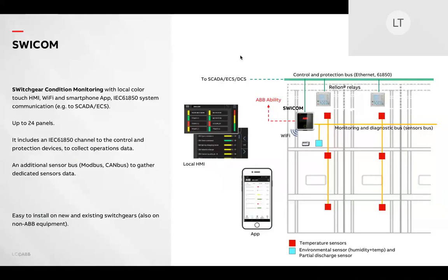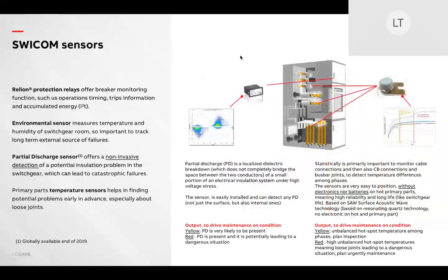SWICOM sensors come in two basic flavors. First, let's look at temperature sensors. These are wireless sensors that are fitted inside your switchgear and again can be applied to any switchgear, either at the factory or in the field at your site, including third-party switchgear. The sensors form a closed-loop system via the sensor, its antenna, and the SWICOM unit.